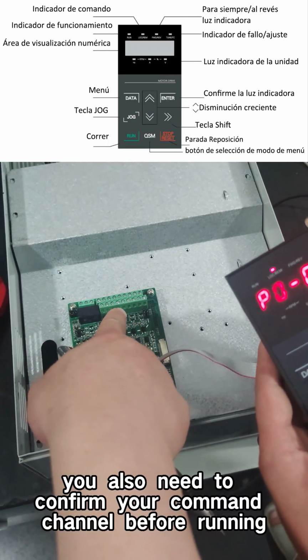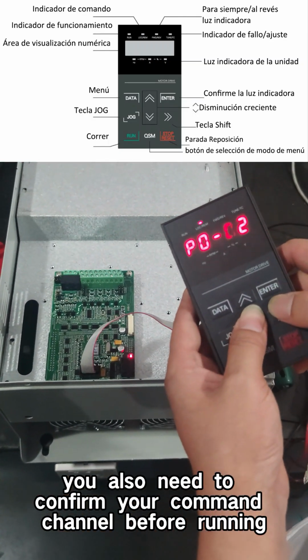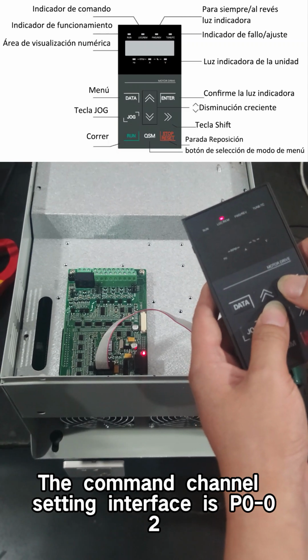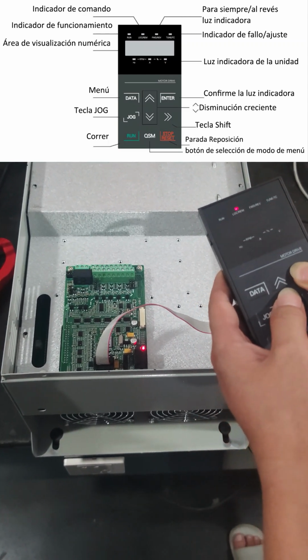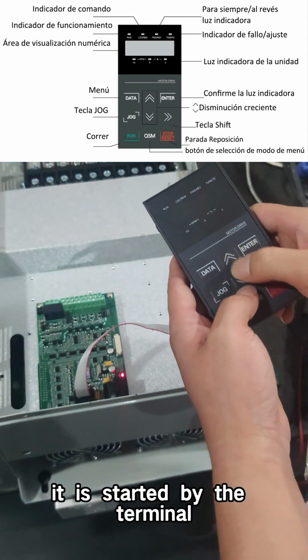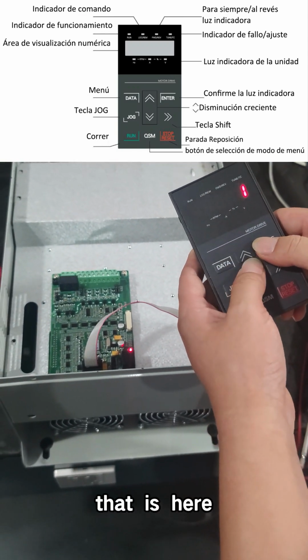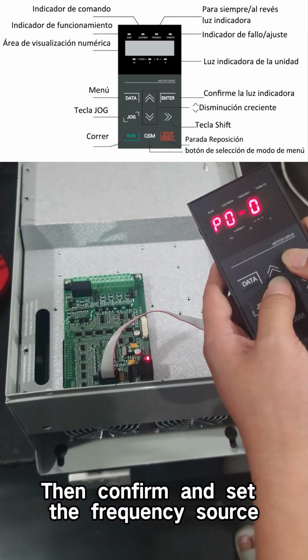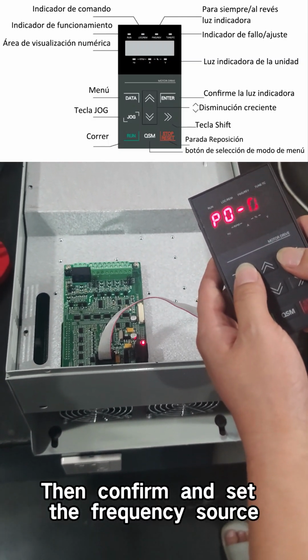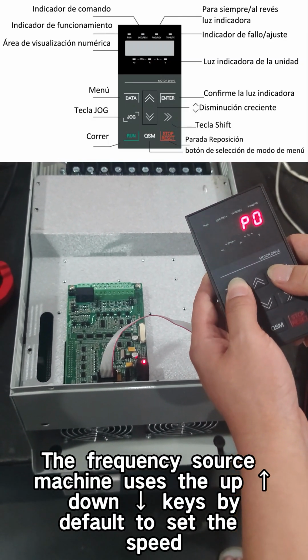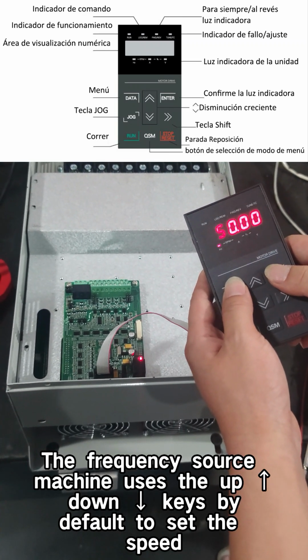Of course, you also need to confirm your command channel before running. The command channel setting interface is P0-02. When the parameter is 1, it is started by the terminal. That is here. Then confirm and set the frequency source. The frequency source machine uses the up-down keys by default to set the speed.